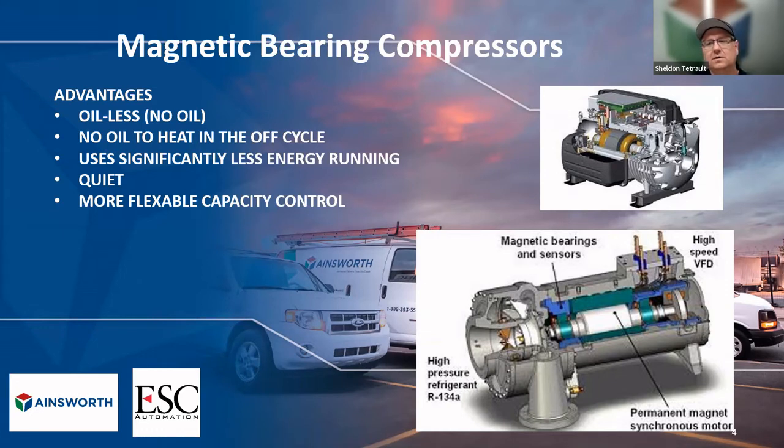So there's no oil, no friction really. And without the oil, you don't have the oil maintenance, the oil changes, there's no oil filter to maintain. And there's no oil to heat in the off cycle. A lot of you have found that if a machine is off for servicing, you need 6, 12, 24 hours to heat that machine back up and make sure the oil is nice and hot before you run the machine. With magnetic bearing machines, there is none of that. They also use, through the reduction in friction, way less energy running.